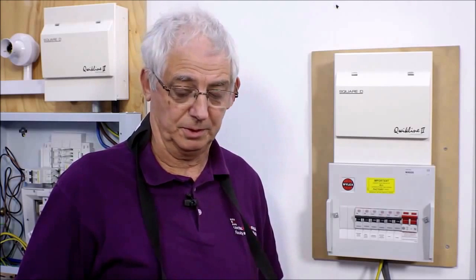remove anything from the system which is likely to be damaged by the high voltage because we're going to test at 500 volts, or even neons which may not be damaged but of course will give us false readings, and then again we'll be looking for a fault that may not be there. So we need to just take care that we prepare the installation ready for test before we test. Okay, so I've done that.